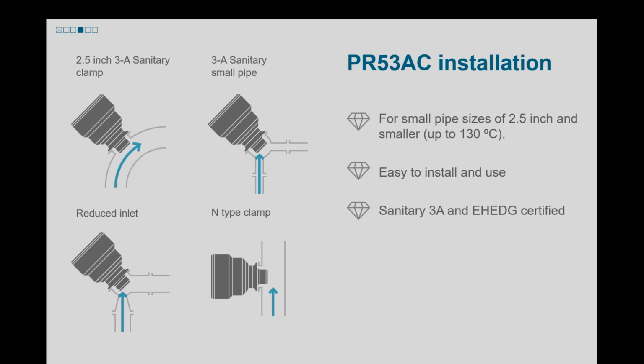The right-hand side shows our flow cells. We even have some reduced inlet to help increase the velocity. In our case, velocity is your friend. Again, it helps keep the sensor clean. We typically like to see 3 to 5 feet per second or higher in applications where there tends to be any kind of a coating.